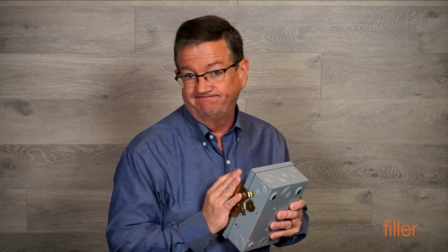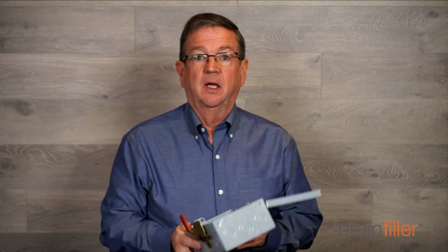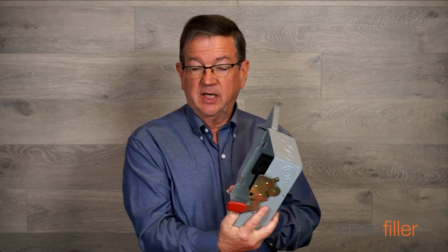Now, some will think, well, we don't do any energized work, so hooray for us. Oh, great. That's exactly the idea. That's priority. But the thing is, in establishing an electrically safe work condition, you're interacting. And you have to verify absence of voltage. And until you've verified absence of voltage, you still treat it like it's energized. And if you treat it like it's energized, that means you need PPE, you need to be aware of the hazards. That's on the label.